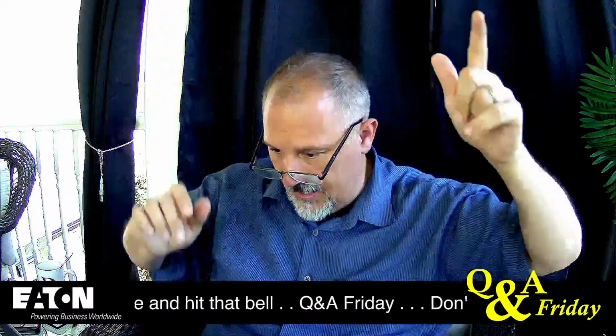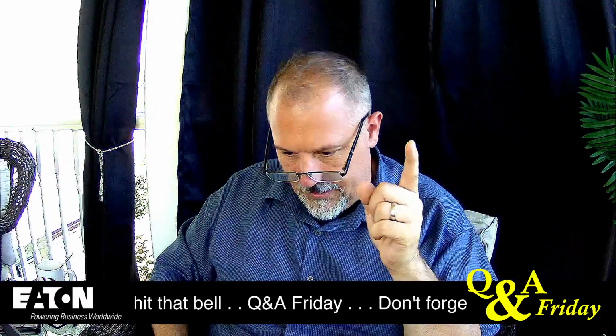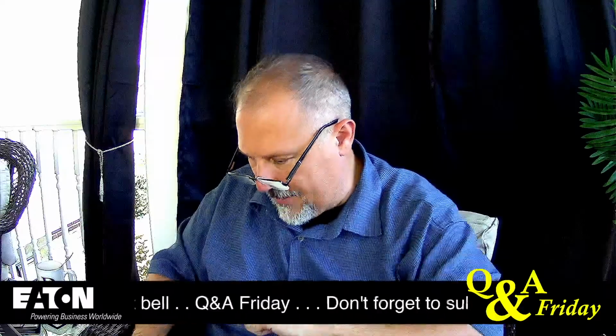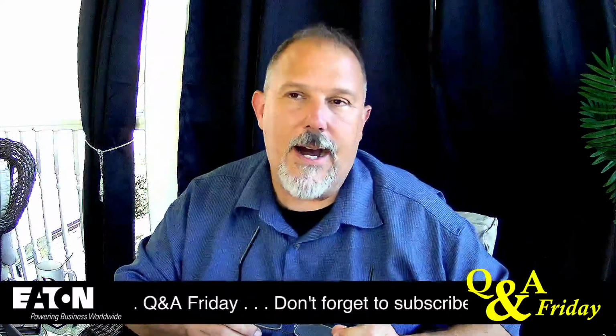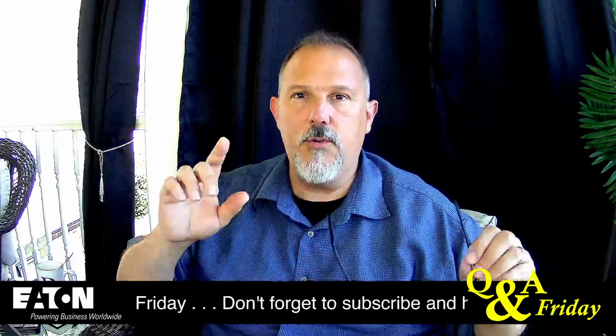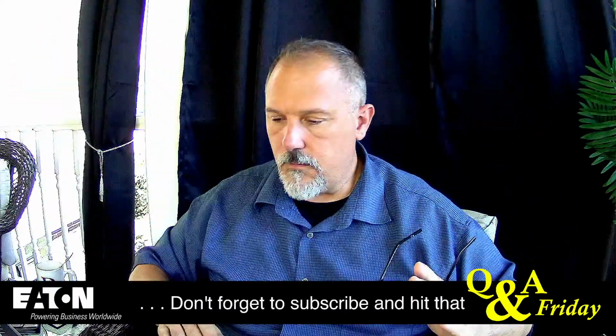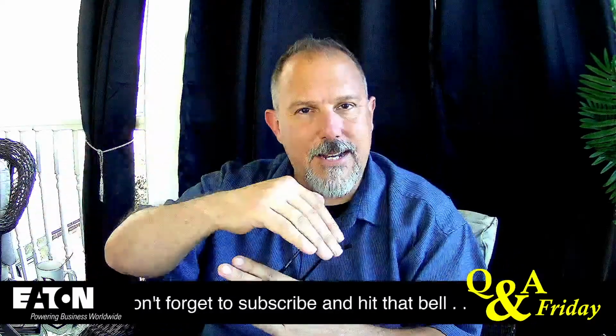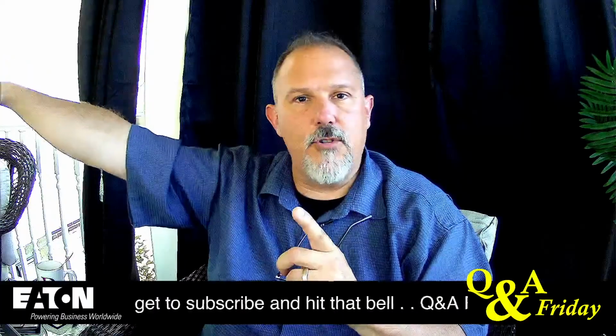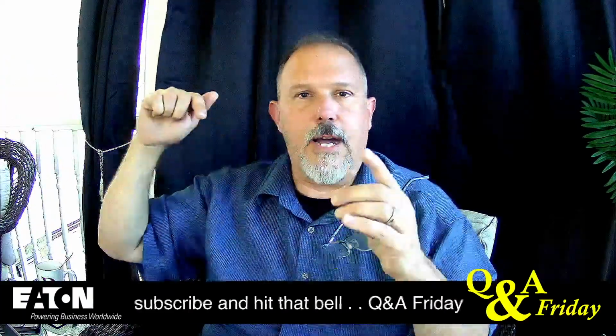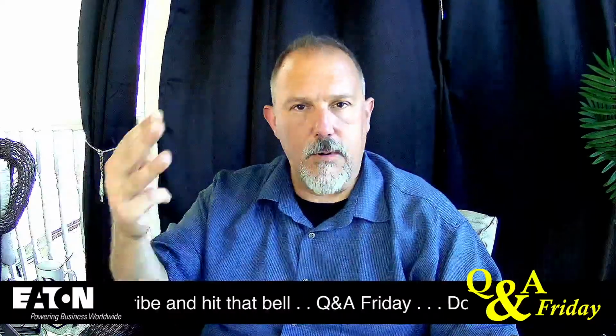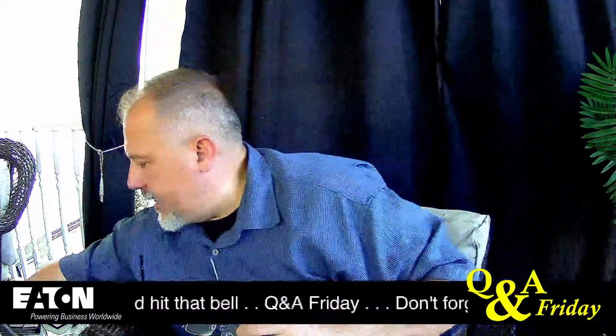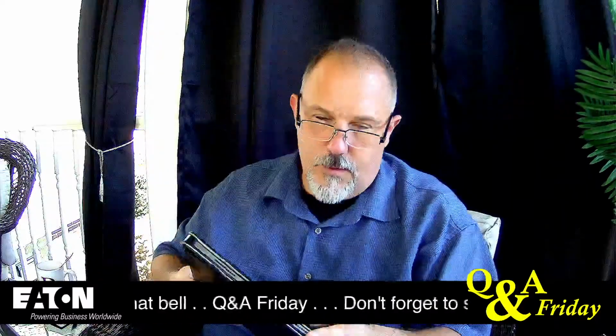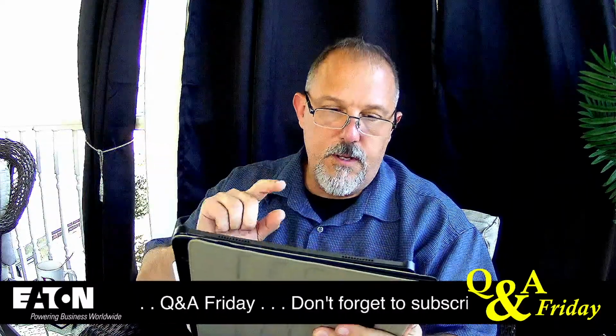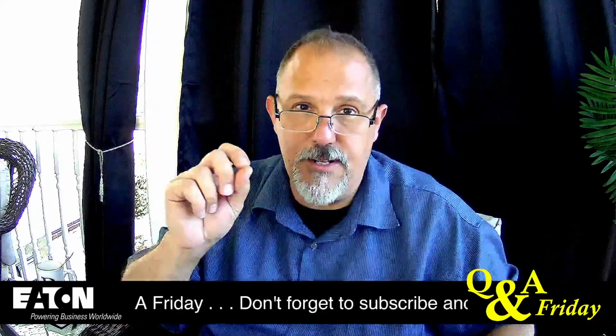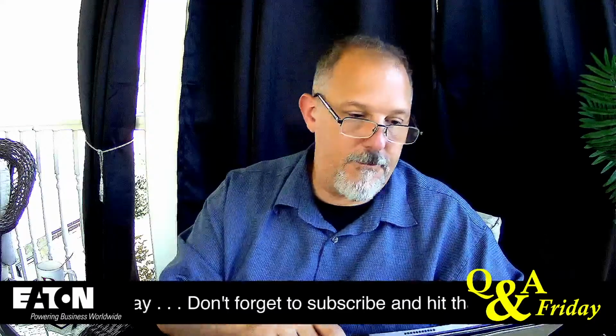Fire pumps. Okay, I'm going to talk fire pumps real quick. All right, so I'll tell you what I did, and I'm going to put this link in there. So here's what happened to me, Phil. I got an email from an individual who was asking questions about the conductor on the secondary, the conductor for the line side tap, line side going down to the fire pump controller. And they said, look, all I need is 3 hots. I don't need a neutral. I got to look back at the exact question. The discussion was around that neutral and whether or not the grounded conductor needed to be there.